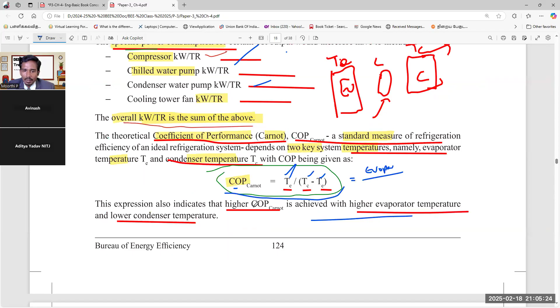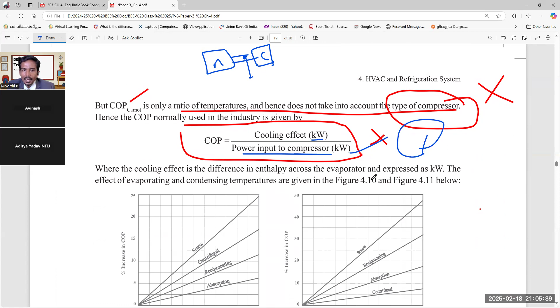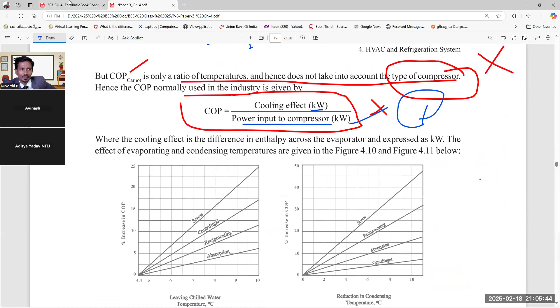Don't change it, you have to convert - suppose it's in TR, you have to convert to kilowatt. Okay, this is the basic formula. Already understood: COP equals the evaporator temperature divided by TC minus TE. Then this is very important - the cooling effect in kilowatt over power input to the compressor. This is another formula we always use. Rarely, we use this formula for a 1 mark question. These two formulas are very important.